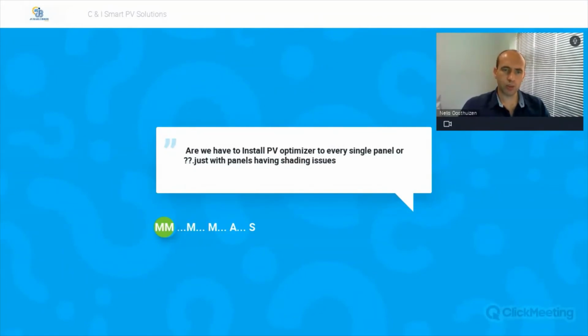Next question from Mohammed. Do we have to install PV optimizer to every single panel or just with having shading issues? So the first answer is you only need to install it to the panels that's got shading issues. So if you've got a 100 kilowatt plant, you've got 10 strings, you do not have to optimize all 10 strings or all 100 panels or whatever your situation might be. You only need to optimize the panels that's affected by shading.